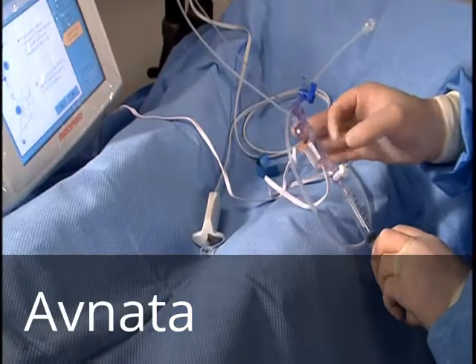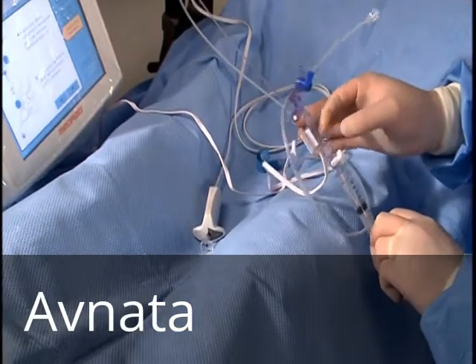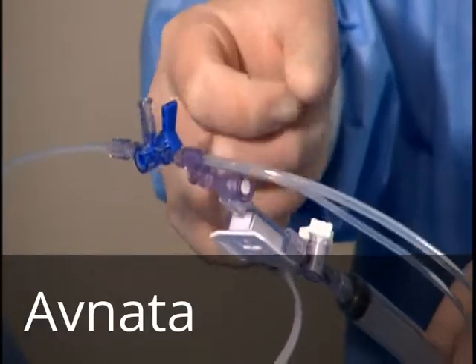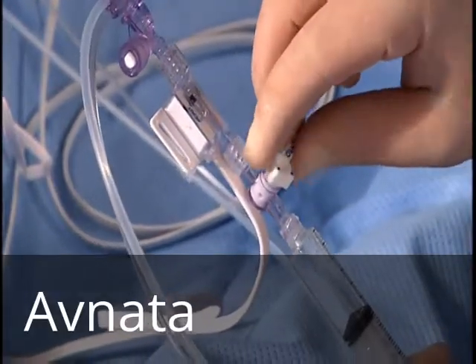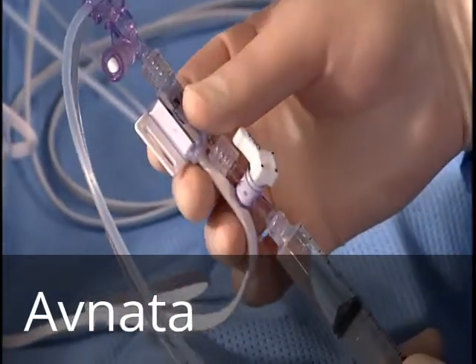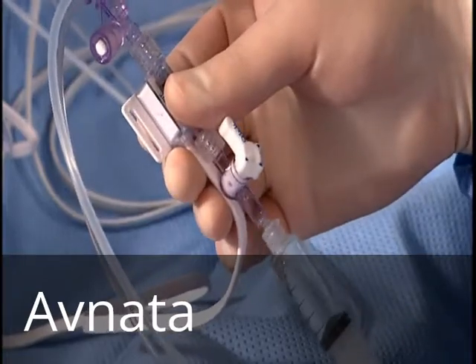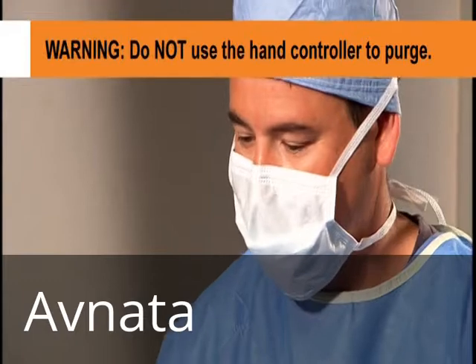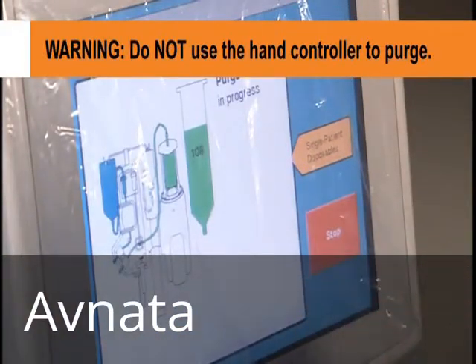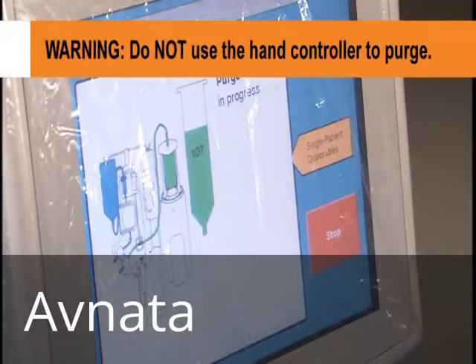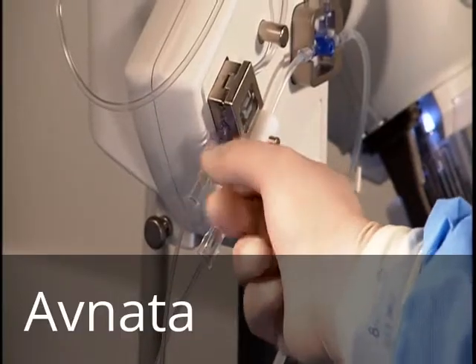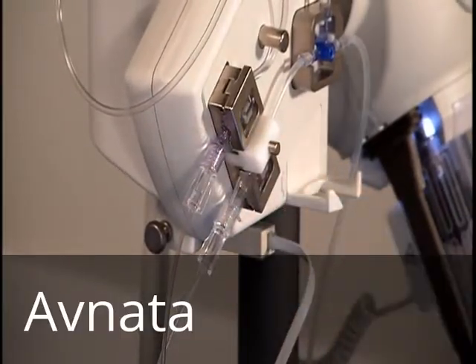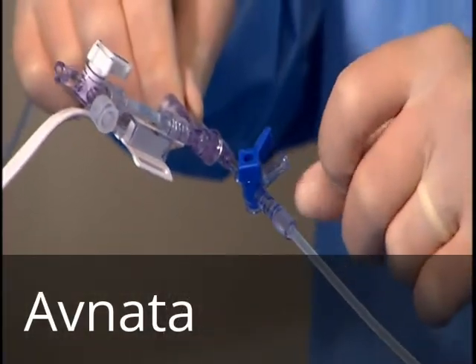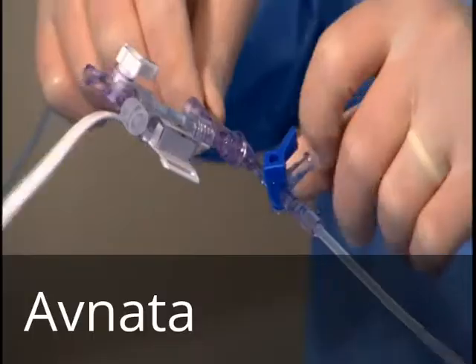Flick or tap the PIV to facilitate air removal, and repeat as necessary. Close the transducer port stopcock and remove the 10 cc syringe. In the setup screen, touch Purge. Initiate a simultaneous contrast and saline purge by touching the Purge button. Flick the SPAT to MPAT saline connection point and waste port stopcock to remove air while purging is in progress.